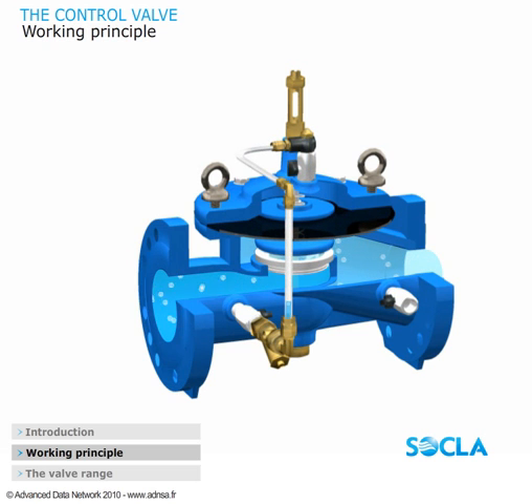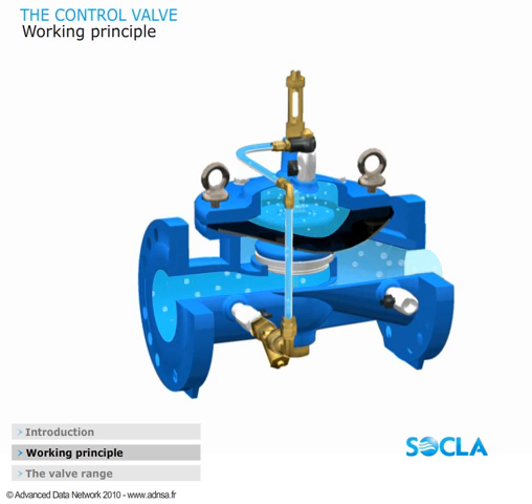When upstream pressure is applied via a pipe circuit onto the top of the membrane, the valve will close. If we complete the pilot circuit with a downstream pressure pipe and a three-way manual valve in order to keep upstream pressure on the membrane of the main valve, it keeps closed.